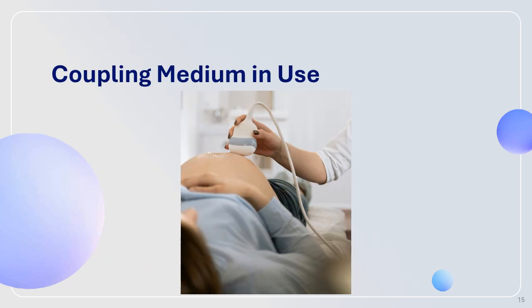Right. So that's a coupling medium in use. I don't know if you can see, but we have gel that has been smudged over the belly. Right. That's the coupling medium. The gel and the tissue have a specific acoustic impedance that is approximately the same.